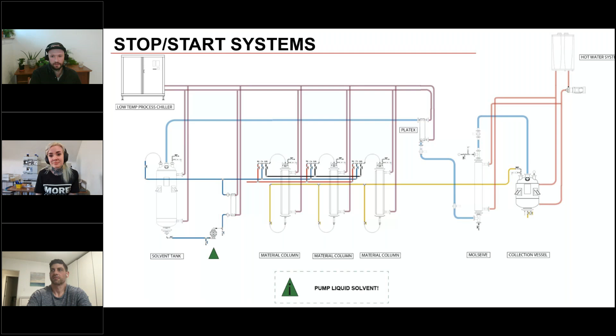Yeah, definitely understanding the vapor pressure in your system is the most core concept for sure. Just the simple fact that, yeah, hot gas wants to be cold. It wants to go to a lower pressure, lower energy state. And so if you have a high pressure area somewhere and a low pressure somewhere, it will go as fast as it can travel through the pipe to get there.